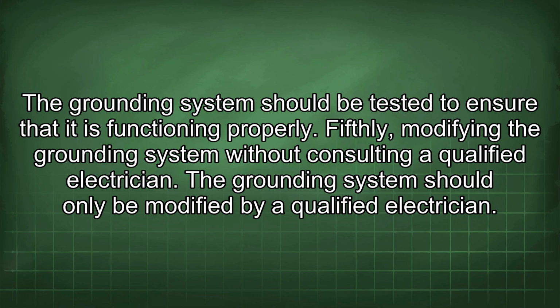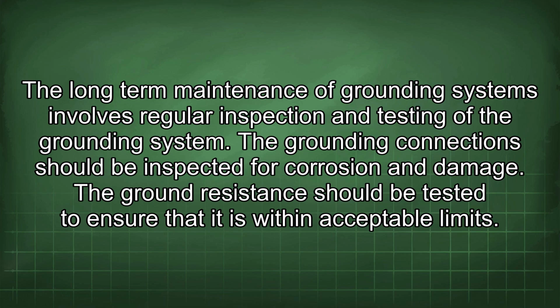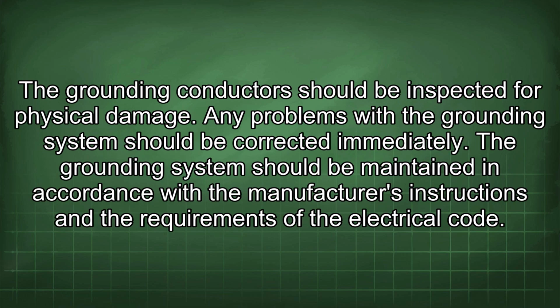Fifthly, modifying the grounding system without consulting a qualified electrician. The grounding system should only be modified by a qualified electrician. The long-term maintenance of grounding systems involves regular inspection and testing of the grounding system. The grounding connections should be inspected for corrosion and damage. The ground resistance should be tested to ensure that it is within acceptable limits. The grounding conductors should be inspected for physical damage. Any problems with the grounding system should be corrected immediately. The grounding system should be maintained in accordance with the manufacturer's instructions and the requirements of the electrical code.